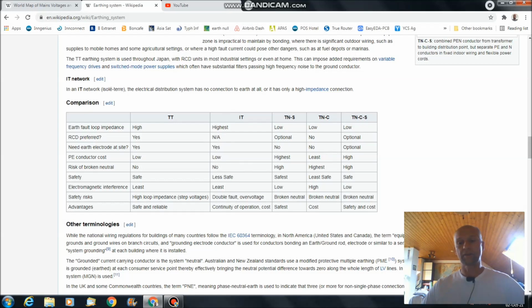And now, of course, this table here is made for grid installations. So that's why you will see here the TN-S system. If you look, need earth electrode at site? No. Why no? Because this electrode is provided by the transformer or at the transformer, and you are getting the PE wire straight from the transformer to your house.